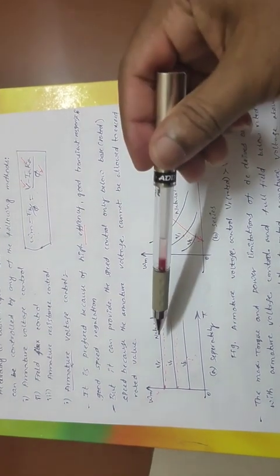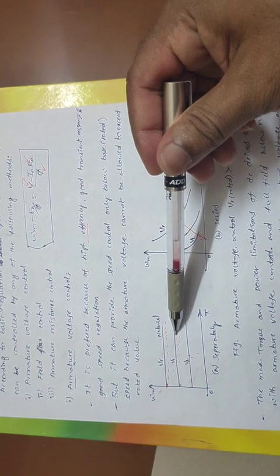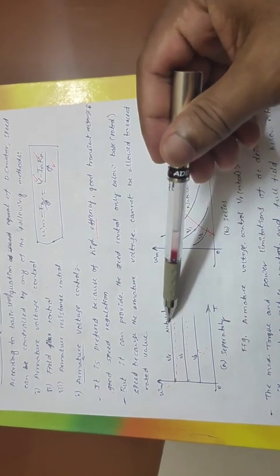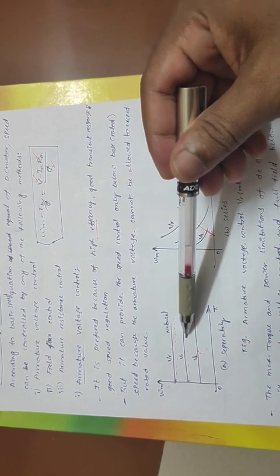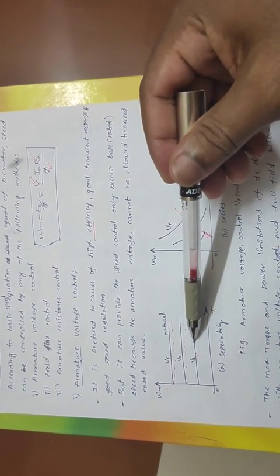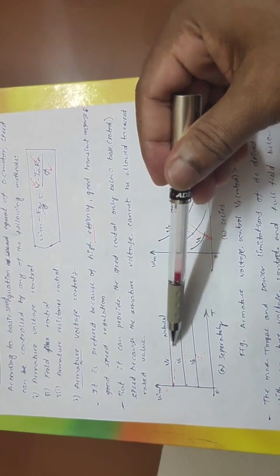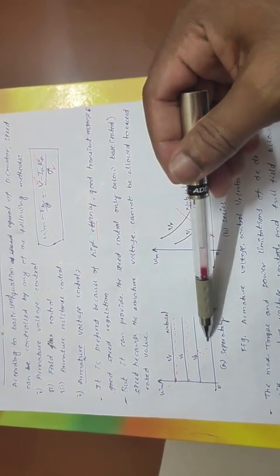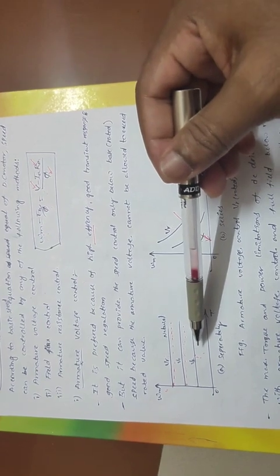When you are decreasing the voltage, VR is greater than V1 is greater than V2. When you are reducing the voltage, correspondingly the characteristics will shift downward. Initially, if we set the voltage at some 200 volts, the characteristics will be at rated voltage VR. If it is 180, the characteristics will shift downward. If it is 160, the characteristics will shift further downward. Likewise, the characteristics will shift downward when you are decreasing the voltage.